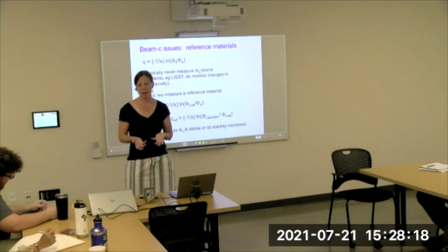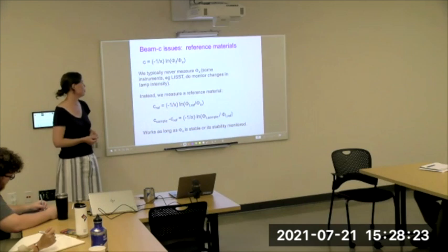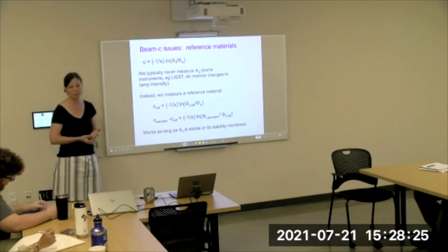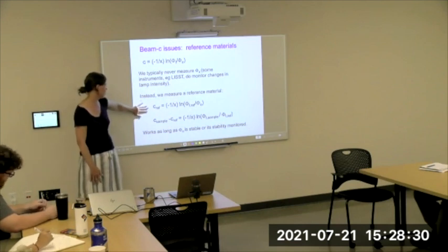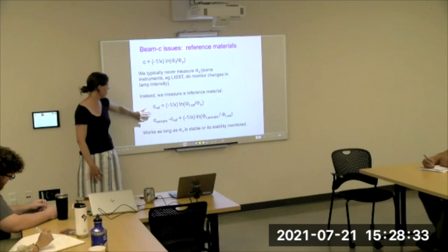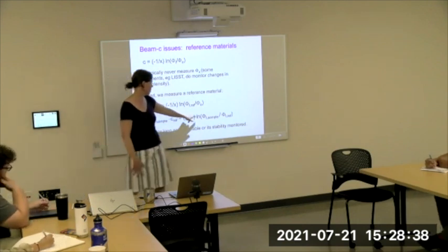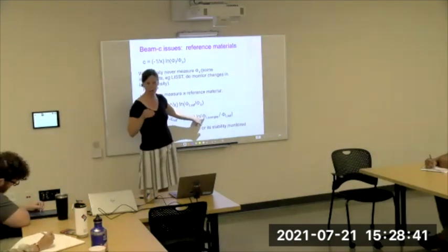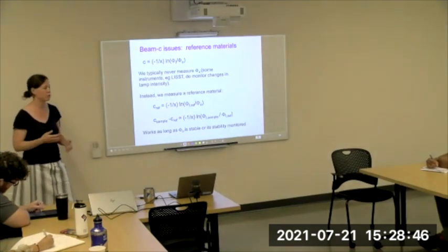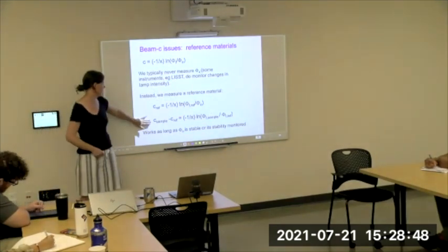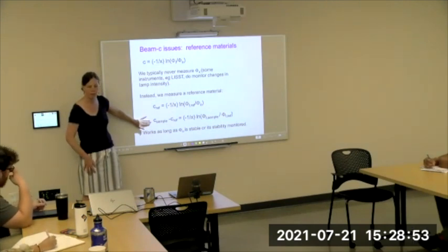So one practice that often gets used for simpler beam transmissometers and AC meters is to use some other reference material, right? So here we are measuring our reference, and then we measure our sample relative to the reference. So the detected light that's transmitted through the sample relative to the light transmitted through the reference material is what we use to compute our corrected sample beam attenuation coefficient.